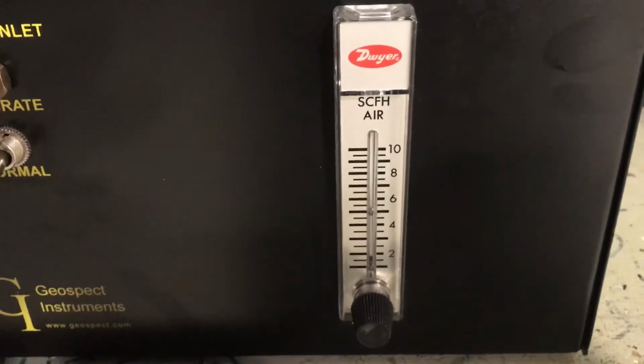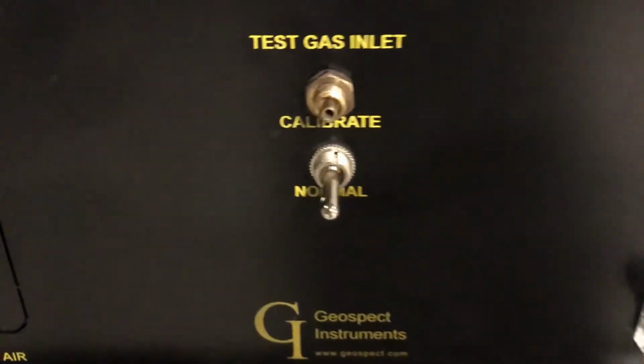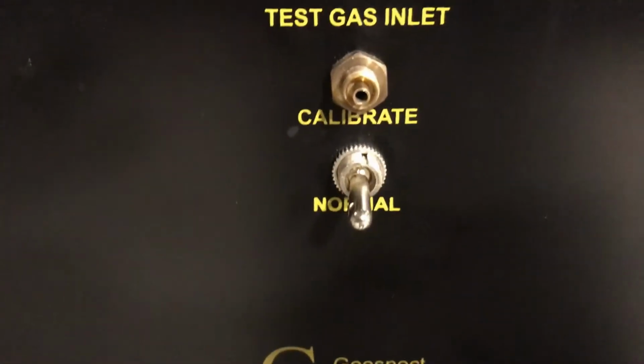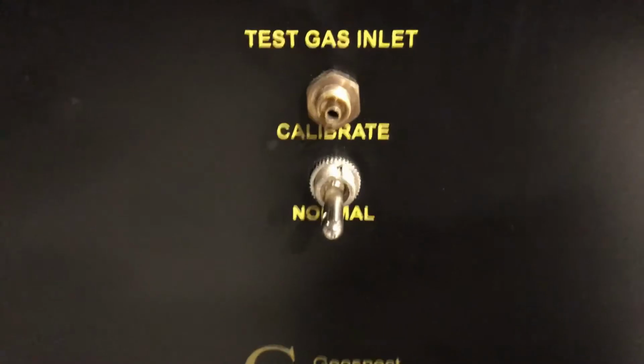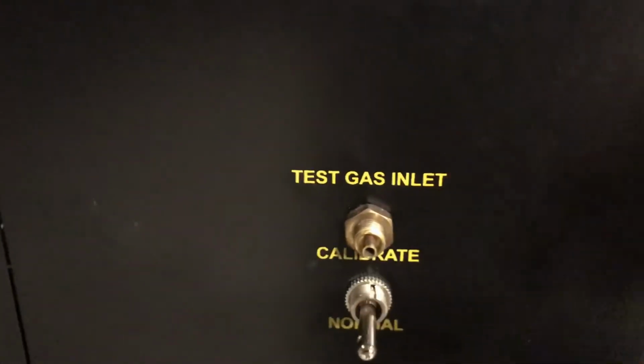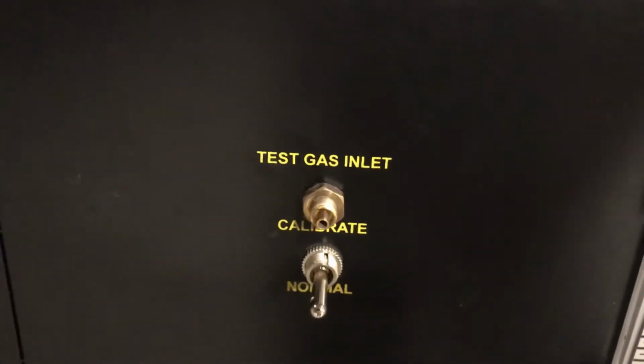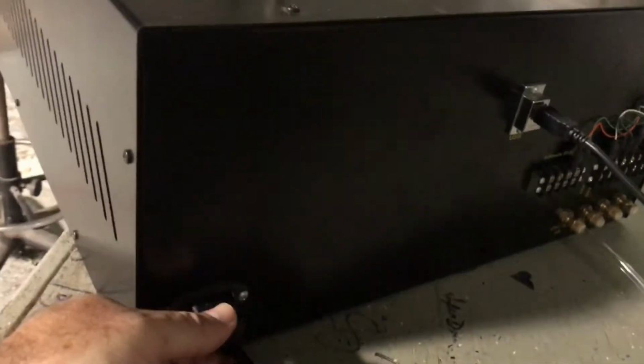On the front here, you have the flow rater for the total gas coming into the unit. And you have a switch which switches from normal to calibrate, and that's just for this test gas inlet, where you can actually put your calibration gas up to the front and switch it and leave your bubble jar connected to the back.